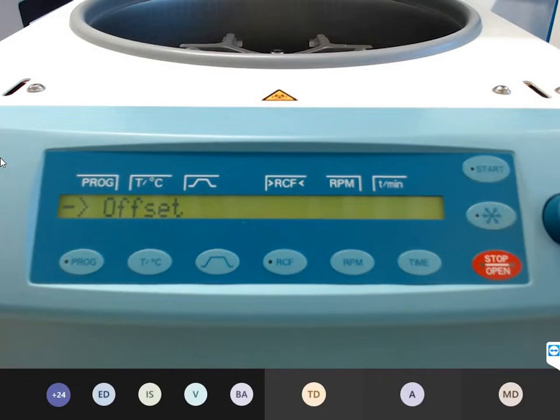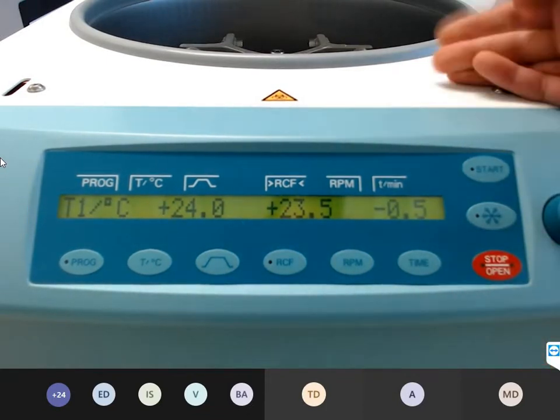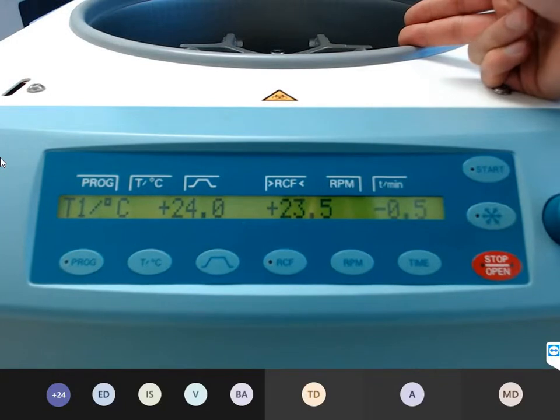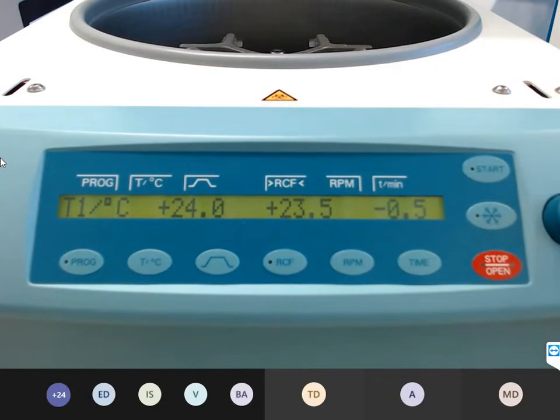Offset values, very important. If you change the imbalance sensor or the front panel, you have to set the offset values again. I repeat what means the offset value. That's the difference between the real temperature and the measuring temperature. We have a manufacturing protocol. If you need the offset values, please write us an email with the type number or the name of the device and the serial number, and we can send you the manufacturing protocol, and on the manufacturing protocol you will find the offset values. That's the same.